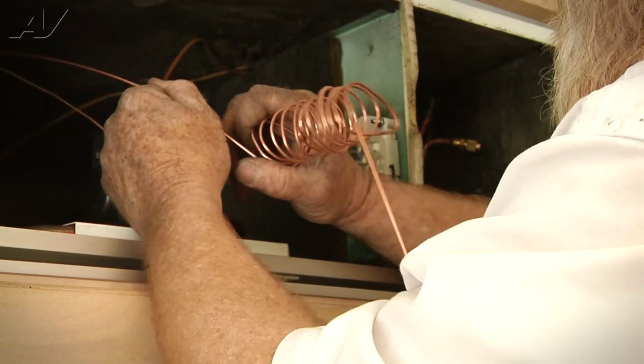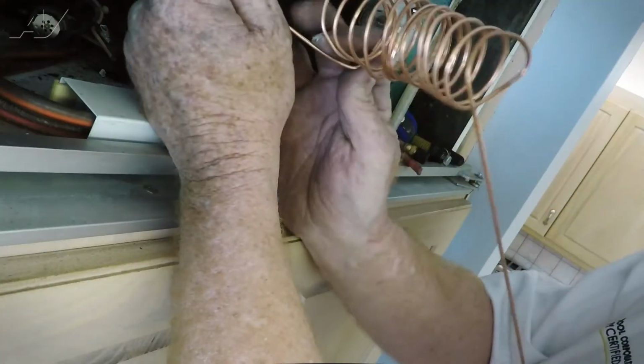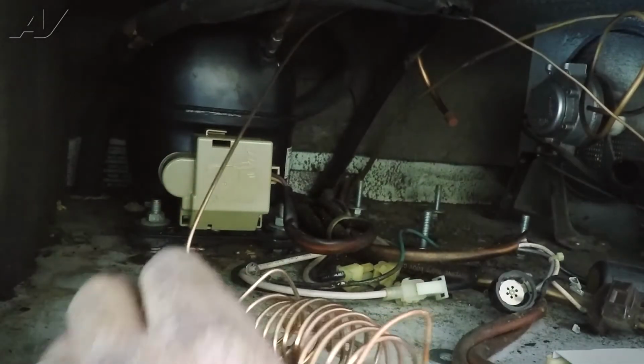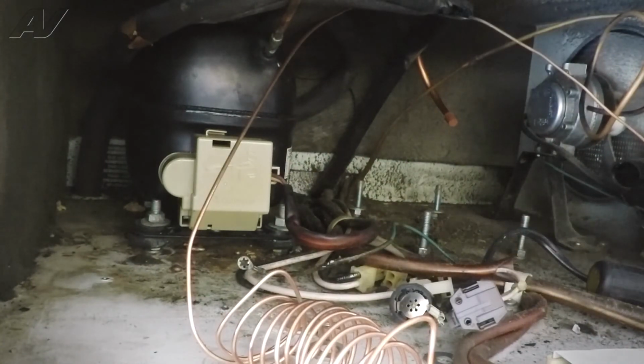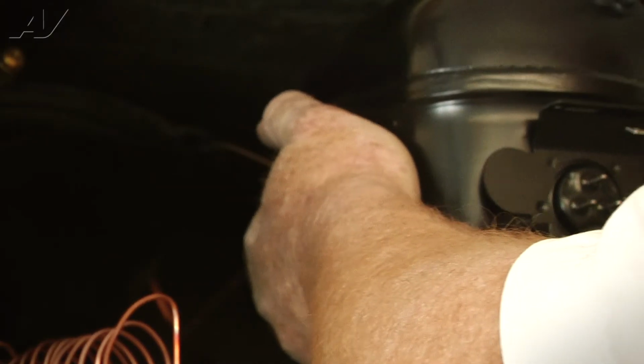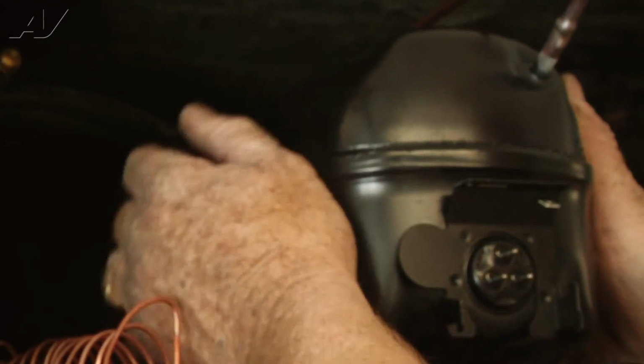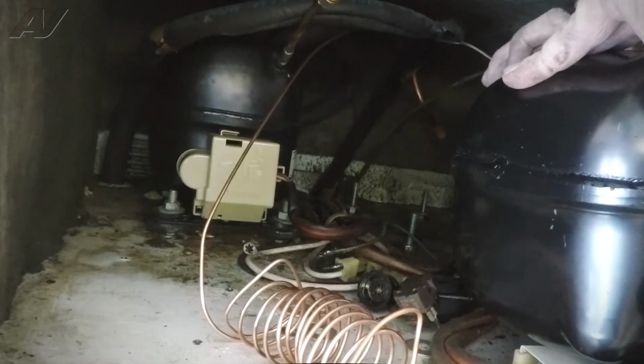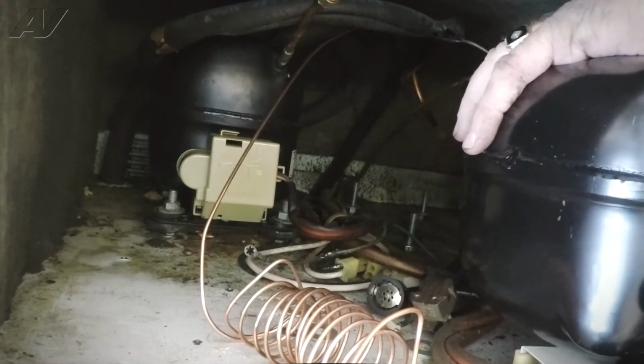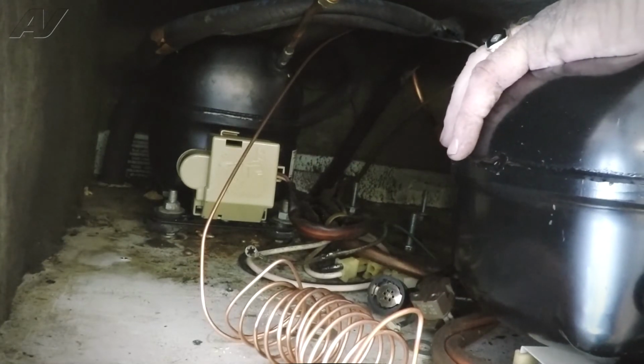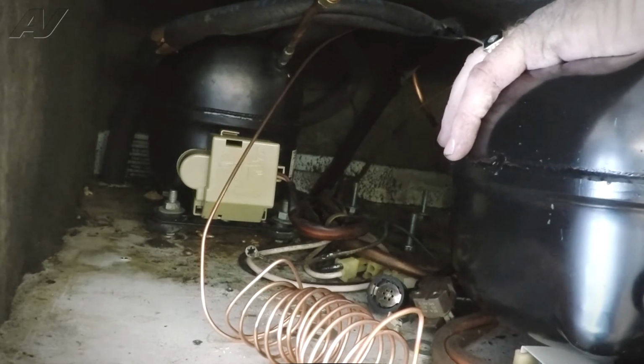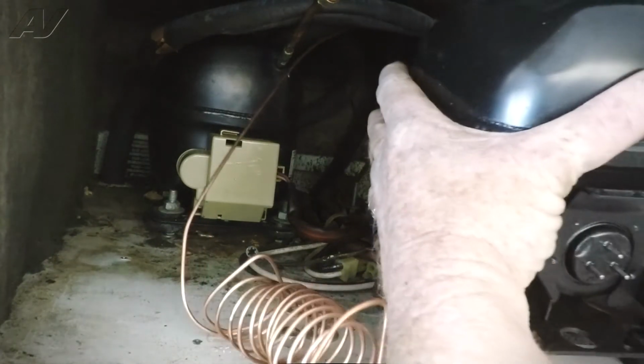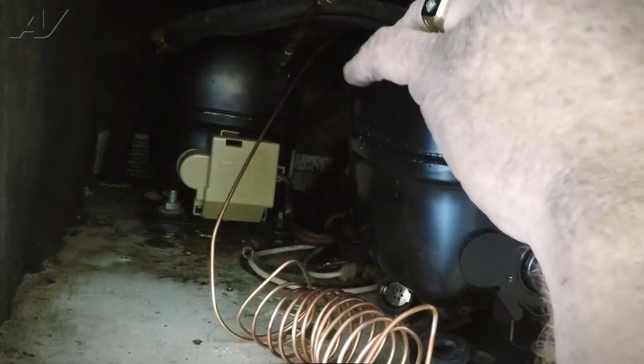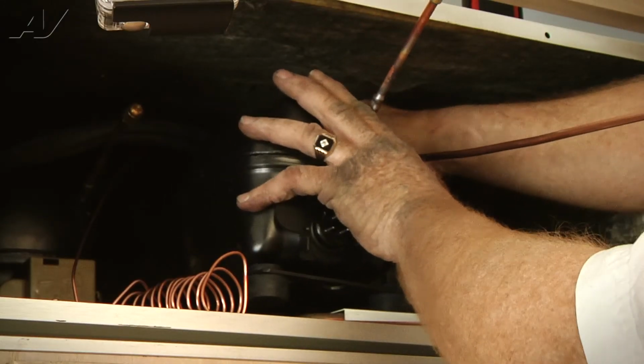Now that we're getting inside the machine compartment, and now that that's wrapped, we're going to bring the compressor in and fit it with the suction line and high side line. So we want to get it over the wires, but under the freezer cap tube.